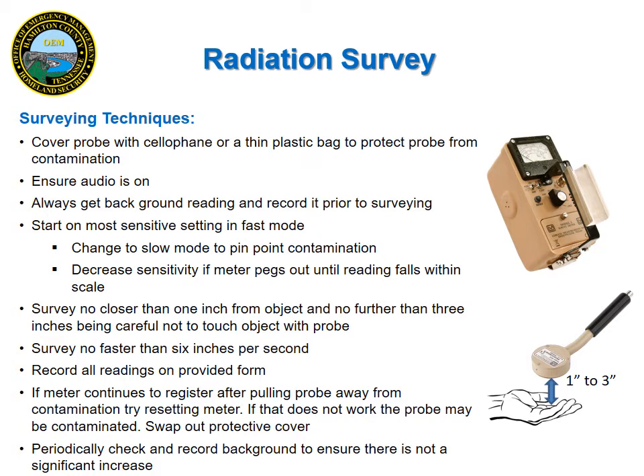In order to monitor properly, you will need to move the probe no closer than 1 inch, but no further than 3 inches away from the skin. Again, try not to touch the probe to someone's skin. You don't want to get it contaminated. So when surveying, you want to make sure that you're moving the probe no faster than 6 inches per second.